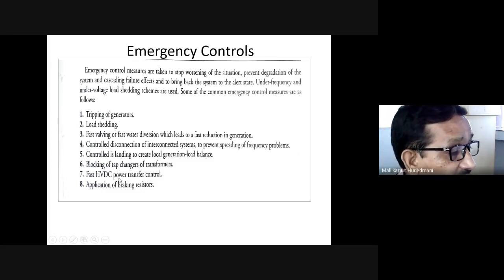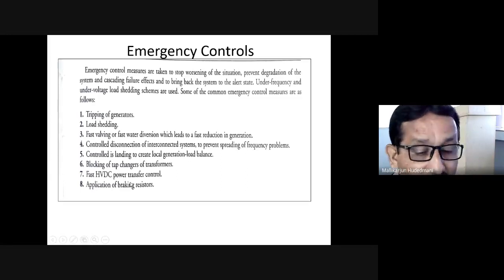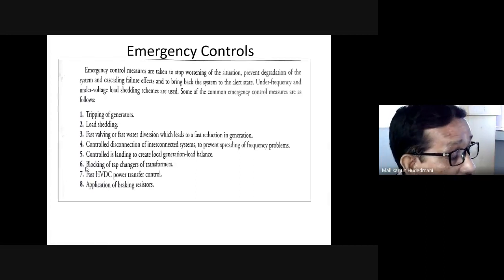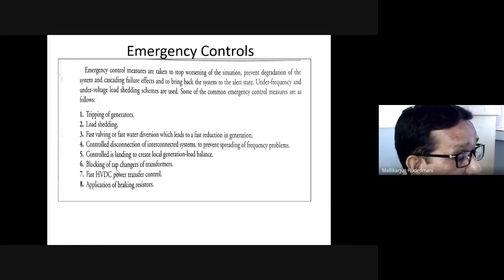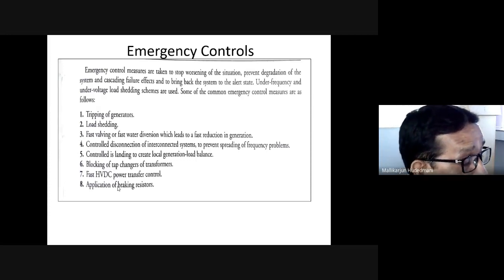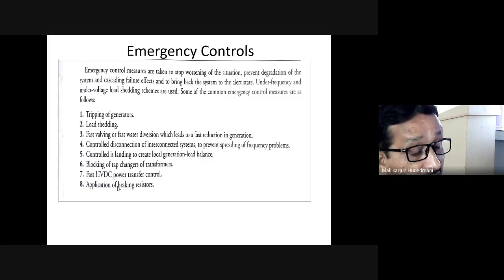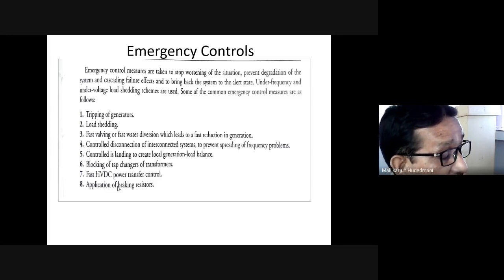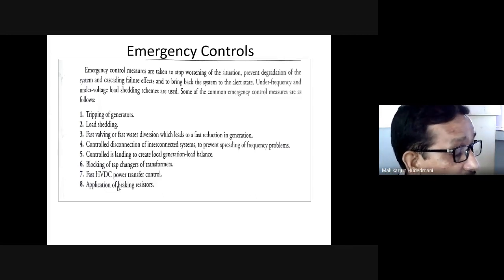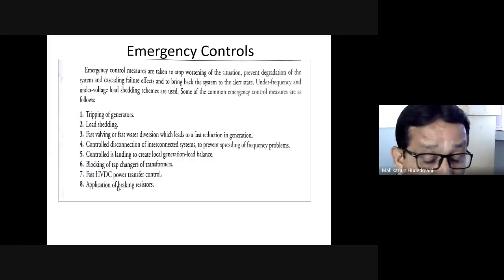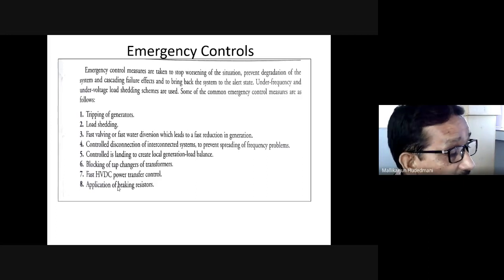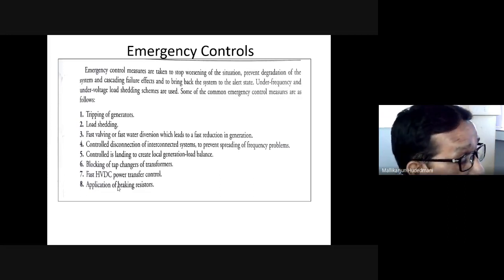Then fast HVDC power transfer control. This is another mechanism. If we have HVDC links connected to the transmission grids, there should be an appropriate control mechanism connected to the HVDC links, which has to be taken care of. Otherwise, the high voltage power equipment and power controllers at the sending end, at the receiving end, at the control side, do suffer due to this. So there must be appropriate care taken around that HVDC link, which makes things controlled, else it is a very disastrous situation, which will be very costly in due course of time.